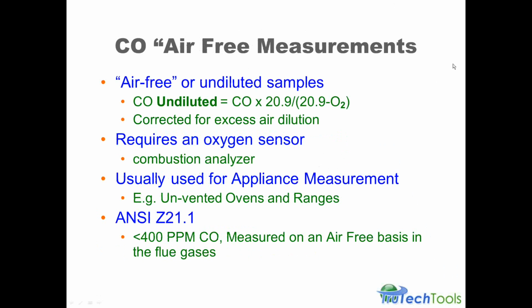Okay, we did promise to talk about CO air-free measurements. An air-free measurement is basically a calculation between the CO sensor reading and the oxygen sensor reading. It's undiluted in that it removes all that excess air due to oxygen by making an assumption about how much oxygen and excess air is present to reduce the CO concentration. So an undiluted CO reading will always be higher than the raw CO reading. It allows it to correct for excess air dilution.